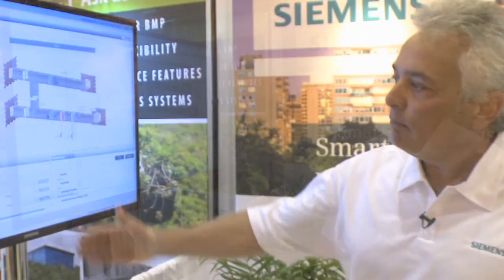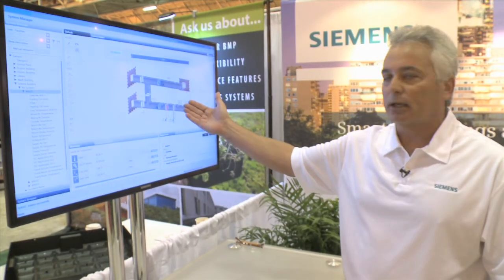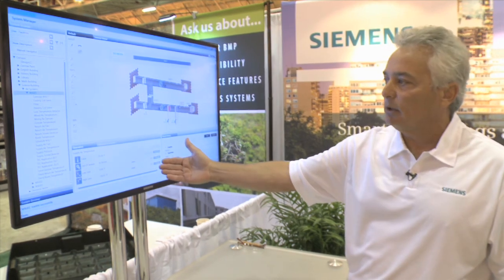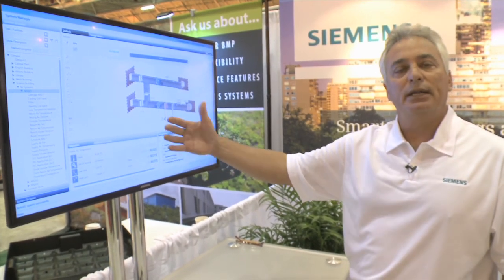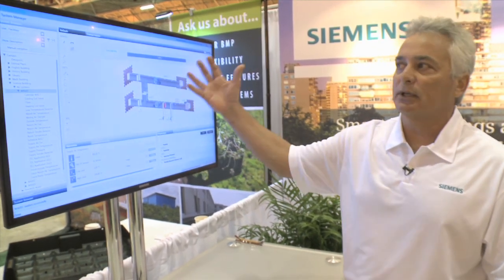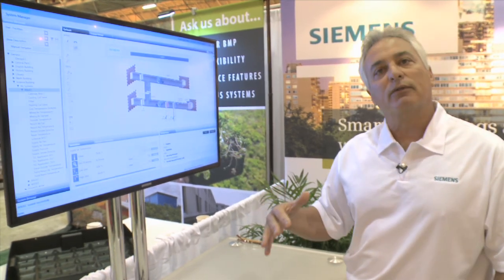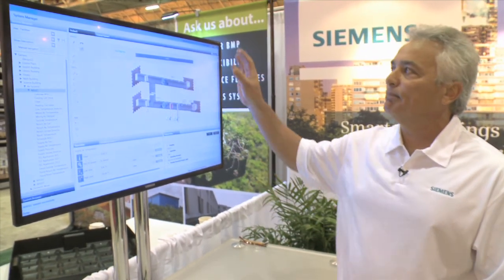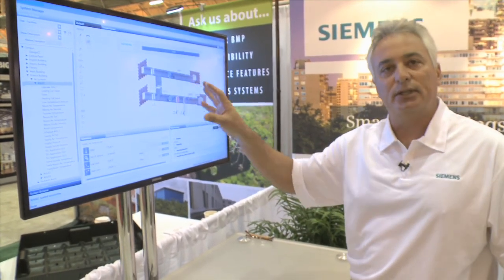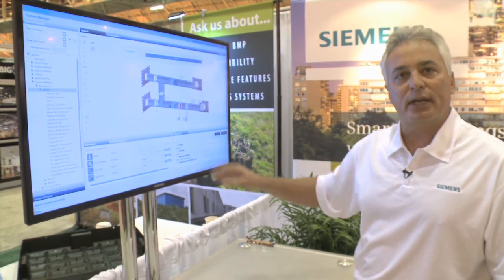for example, you now see that in the operation pane, all the information about that particular device or I/O point comes in. I can change the high and low limits, I can change the value, any other parameters that are commandable or configurable for that device. So this workflow in a central application makes it very easy for a customer versus in older versions of workstations where they had to pick through icons or other browser techniques, different editors and different things to do. It's all on one screen now, so we pick a device and it gives us all the things related to it.